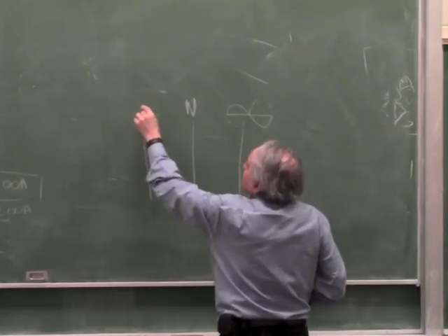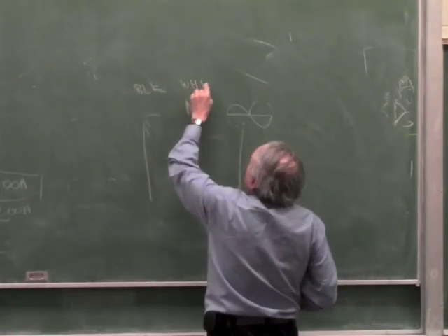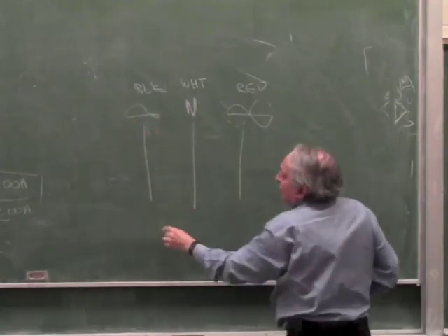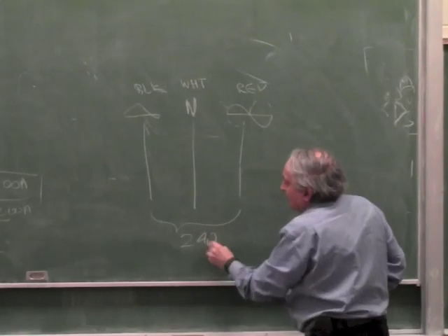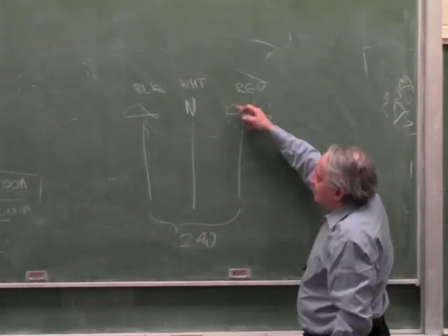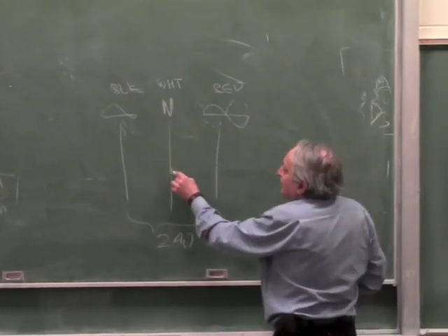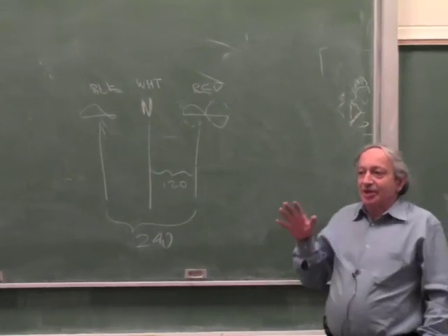One phase looks like this, and the other phase is the opposite. This one is usually black, neutral is white, and this is typically red or blue, and there are two phases apart. So if you look between the two phases, you get 240, because when one is plus 120, the other is minus 120. If you look between a neutral and a phase, you get 120. And that's how all the breaker boxes work.